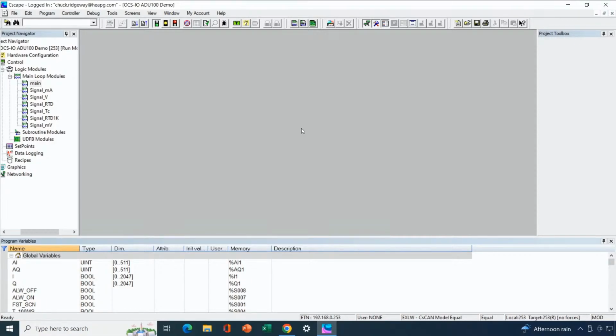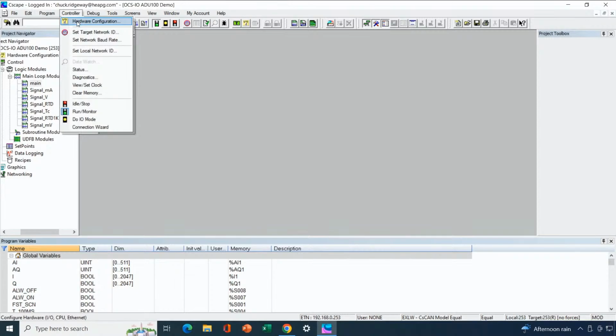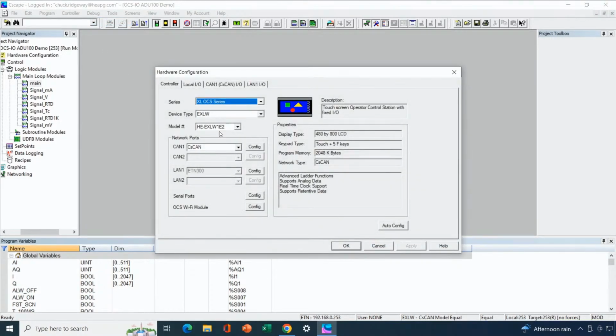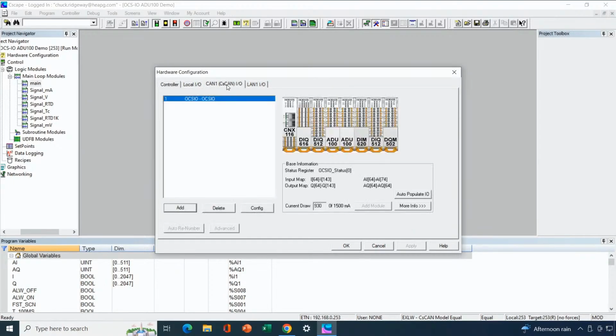Now let's take a look at ADU 100 configuration in Cscape. So I'm in Cscape, got my project open here. And to do configuration on the ADU 100, we need to go to our hardware configuration area, which I can access from this icon, or I can go to the controller menu and select it from there. Next, I need to go to the CAN IO tab that contains my OCS-IO rack.